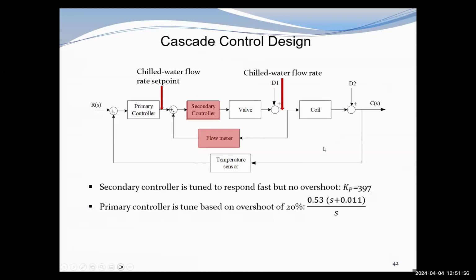Another approach: for the gain scheduling approach, our main purpose is to compensate the cooling coil gain variation. And another approach is to use the cascade control. To design the cascade control, we will add another controller and also a flow meter to create the inner loop. And the cascade controller will be able to reduce the impact of the DP change and also help to compensate the control valve nonlinearities.